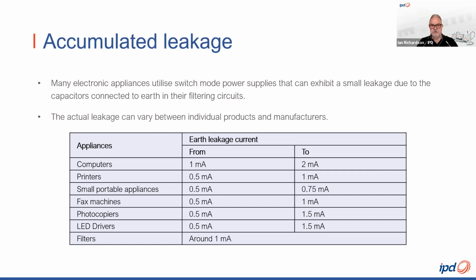Well, as it turned out, long story short, on this particular store, they had changed the brand of LED driver they were using. And it turned out that that driver had a higher leakage than the previous ones they were using, probably because they used a cheaper one. And it all just makes sense. So guys, when you're finding that you've got an issue with a tripping RCBO, number one, check the circuit, find out why it has tripped. Sometimes it's very, very hidden and it can be due to an accumulated leakage. So always look to the load to see if you can determine where the leakage is coming from.